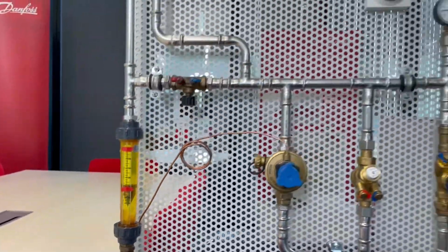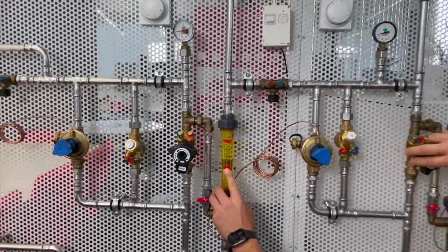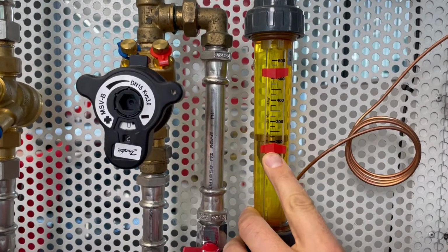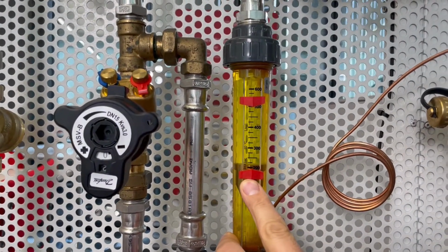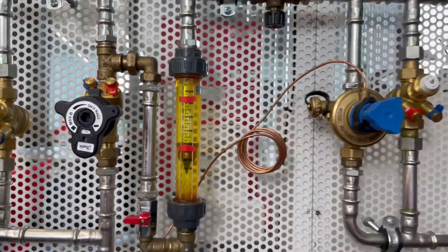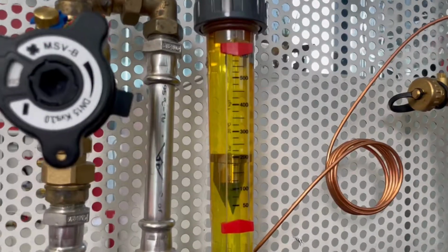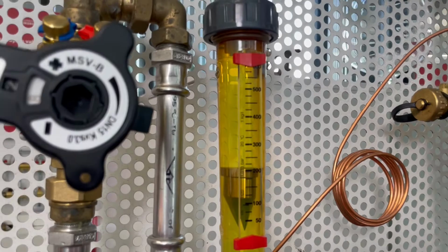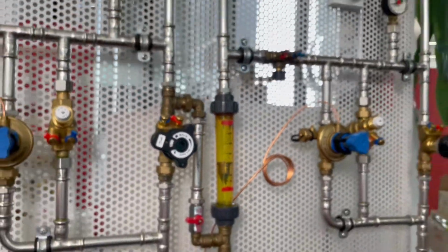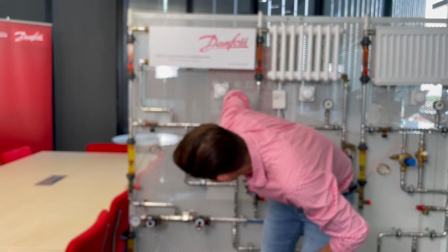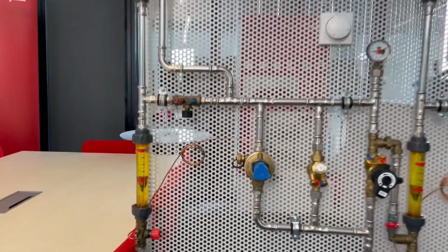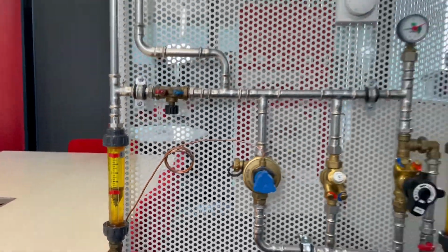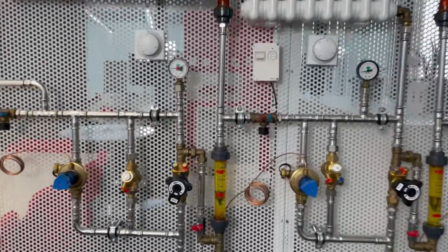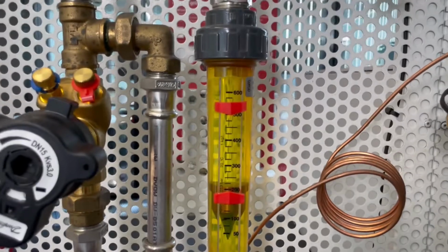Okay, first riser is balanced. Now I balance the second one. I squeeze the balancing valve and set 200 liters. Okay. The last one was 180 liters. Squeeze maybe a little bit just to have precisely 200 liters. Let's check the first riser. Does it change? Oh, it changed maybe a little bit, so I adjust a little bit, the second one a little bit. Okay, so we have now 200 liters at each riser. The system is balanced, and now each riser gets the needed heating capacity.